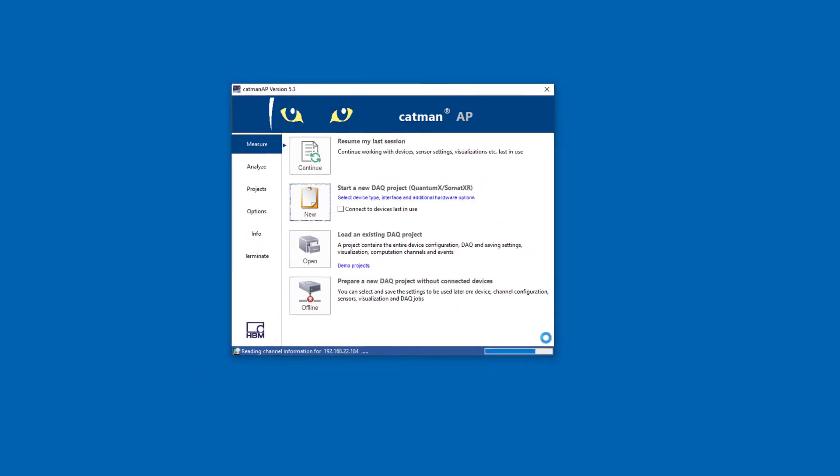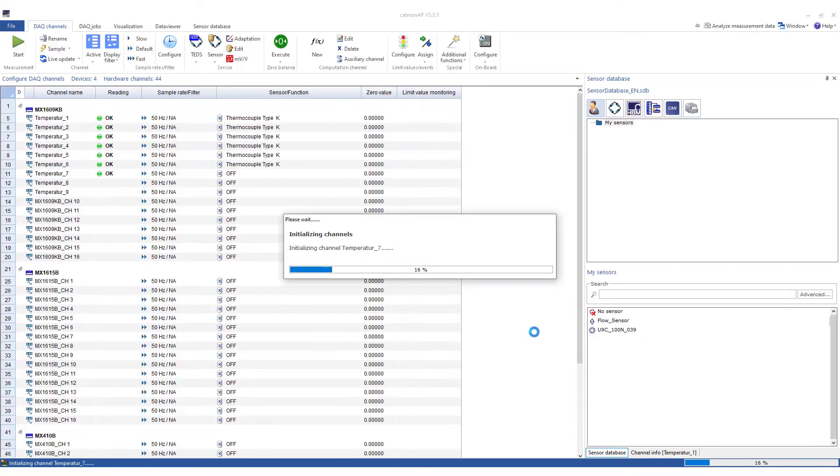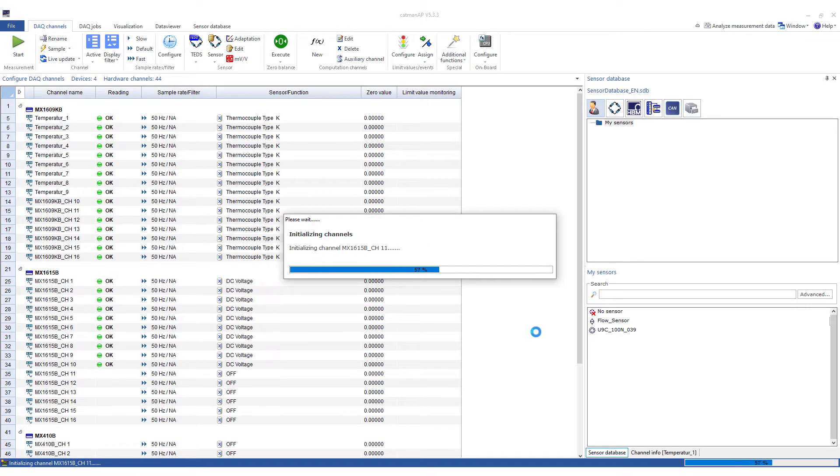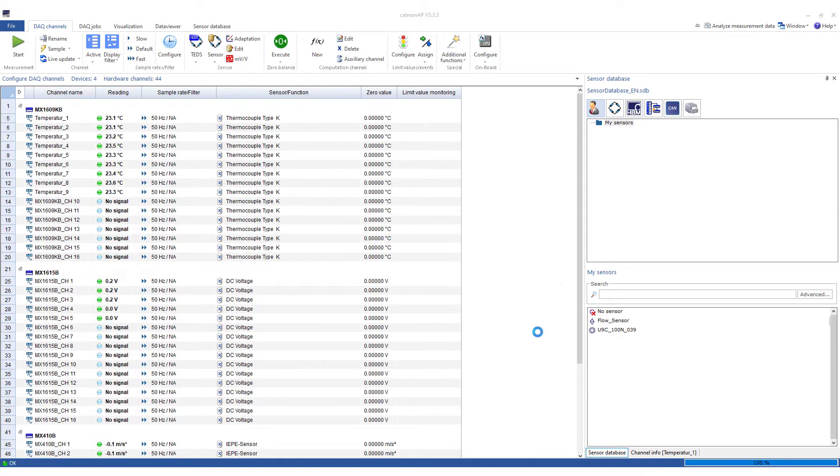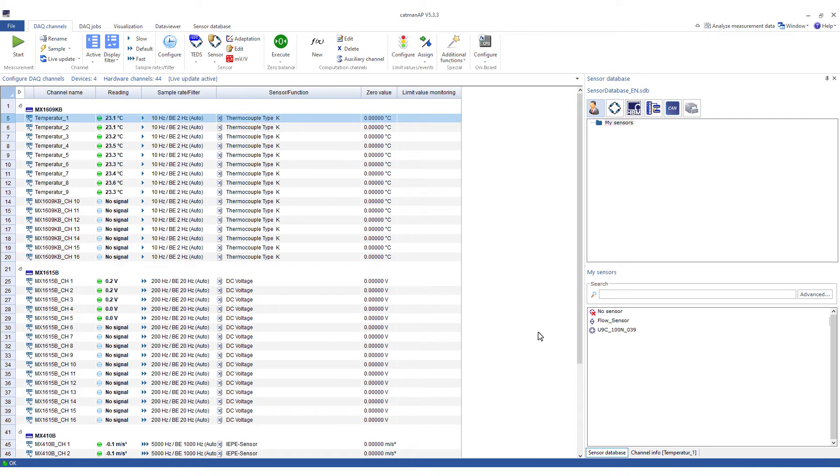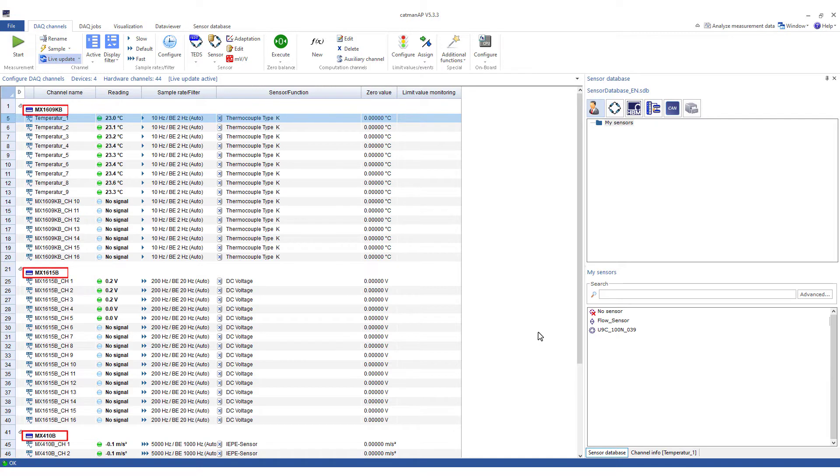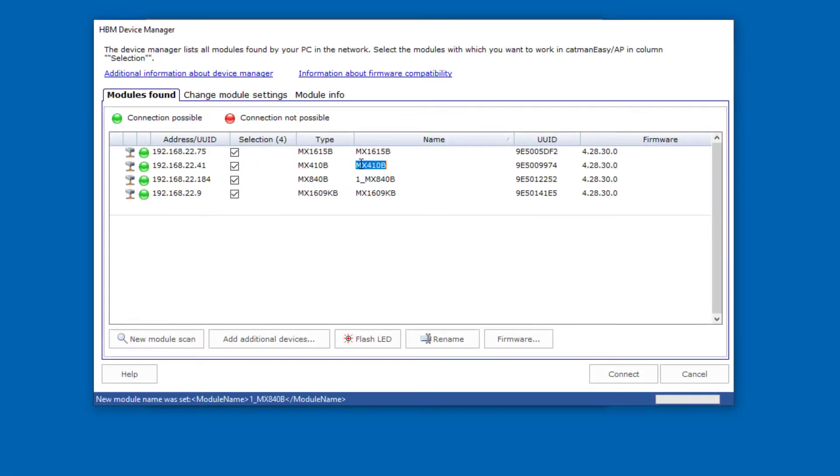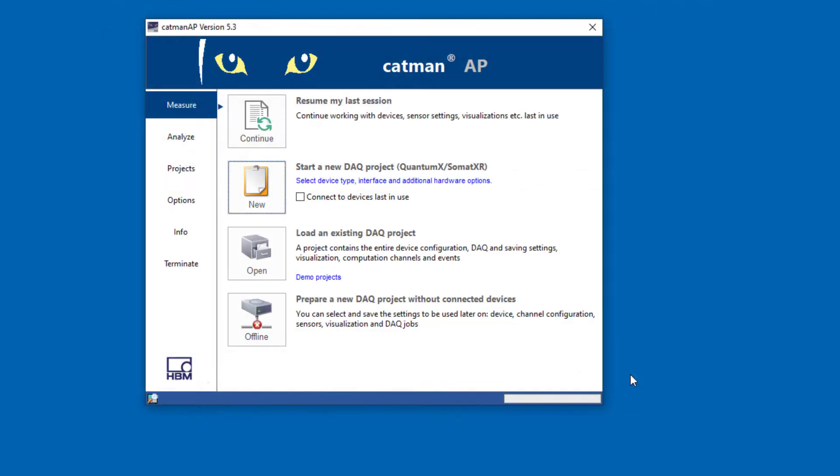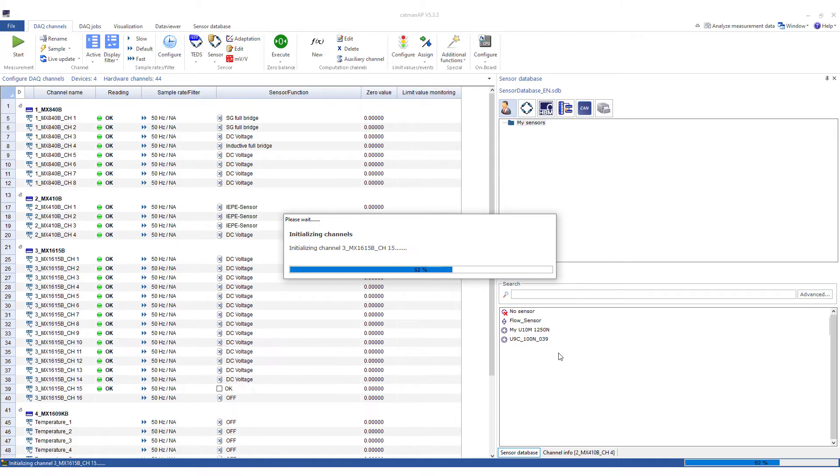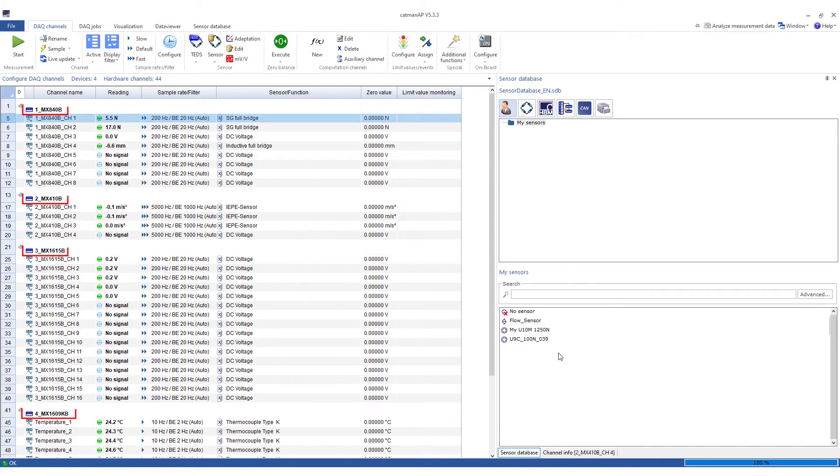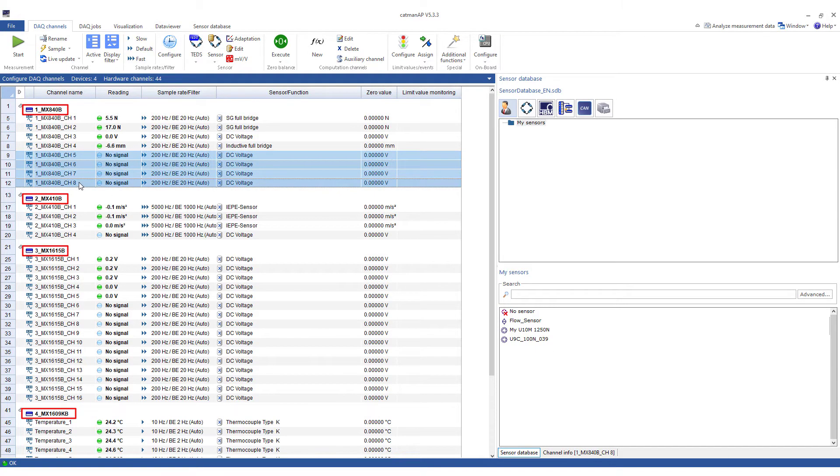When you have connected to the desired modules, the channel list is built up in Catman. All measurement channels are displayed so that you can assign sensors and sample rate groups. As you can see, the created modules are sorted by module names. If you want the modules in the table to be sorted differently, change the default names before connecting. A meaningful name could look like this. I have just done this and reconnected. Therefore, the modules will now be displayed in the desired order.